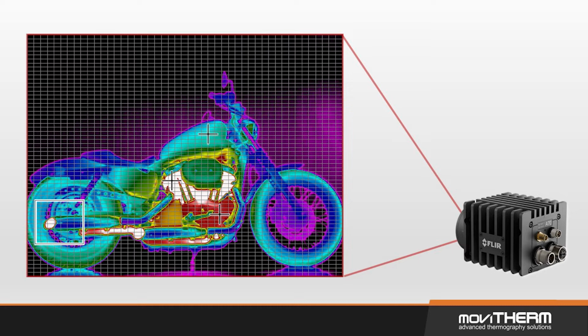Most of the ones that you'll see out there are microbolometer based cameras. We can think of each individual pixel as being a small constrained beam made out of a thermoresistive material. When thermal energy comes in and heats it, it creates a resistance change. We simply run a constant current across it, measure its voltage change, and then calibrate that out for temperature, and represent that as an actual image on the screen, either on the camera or on a screen on your laptop or computer.